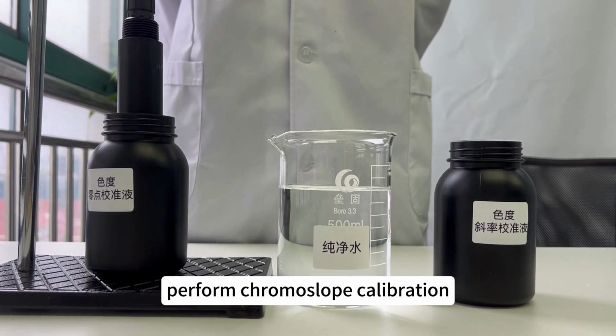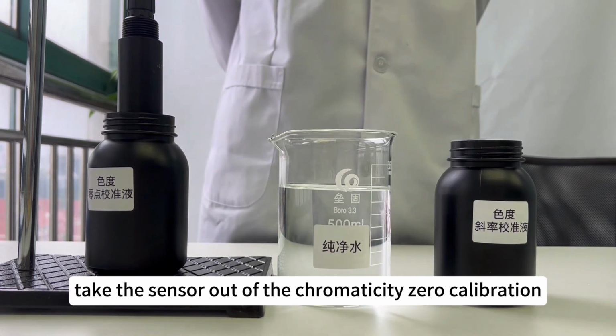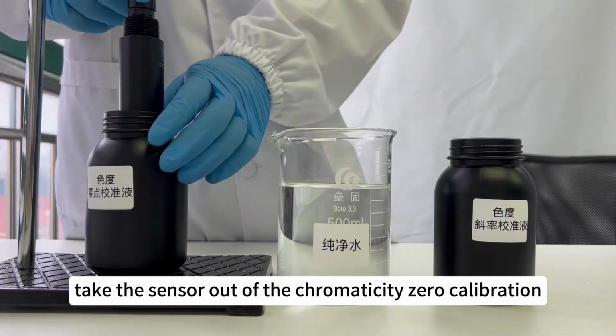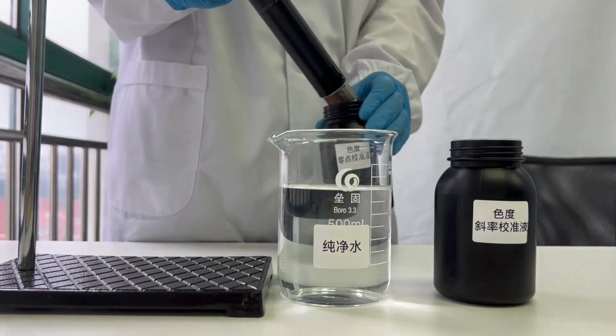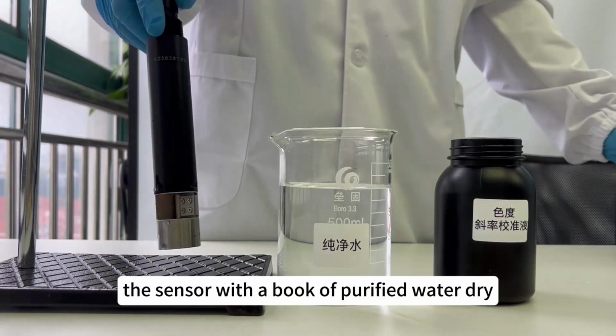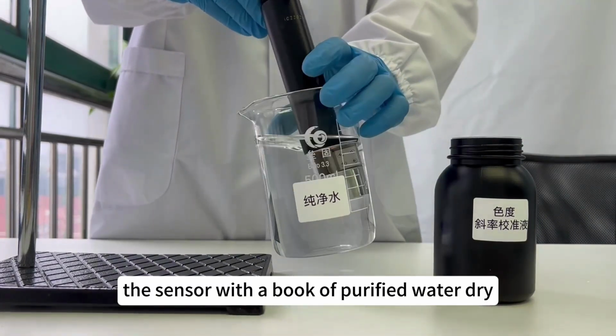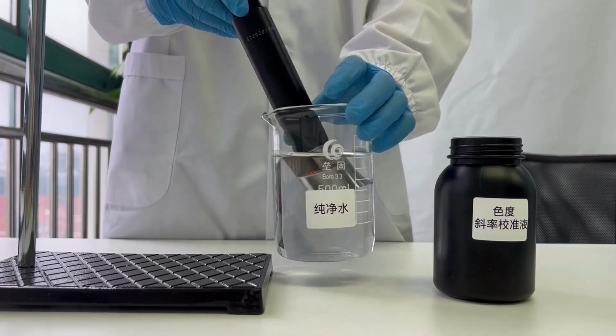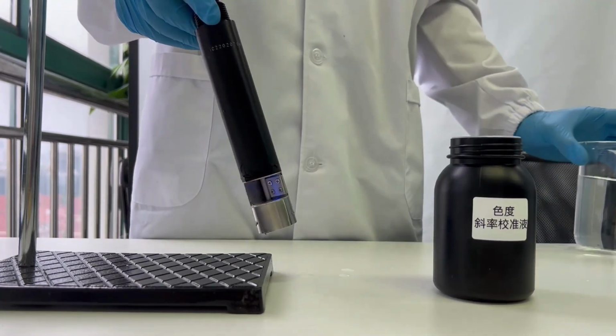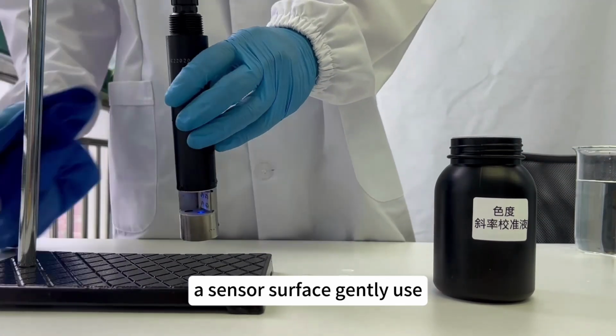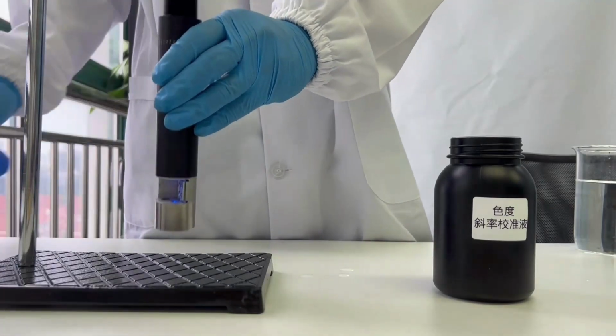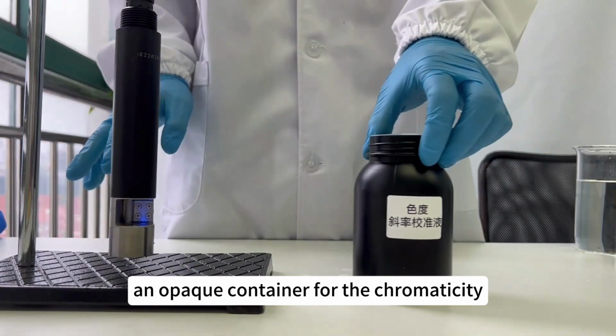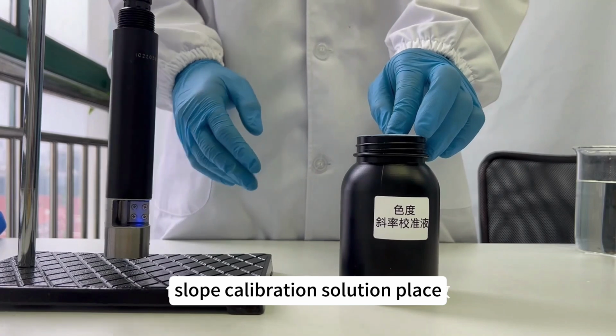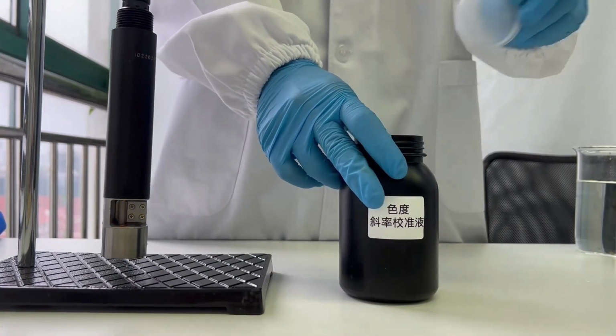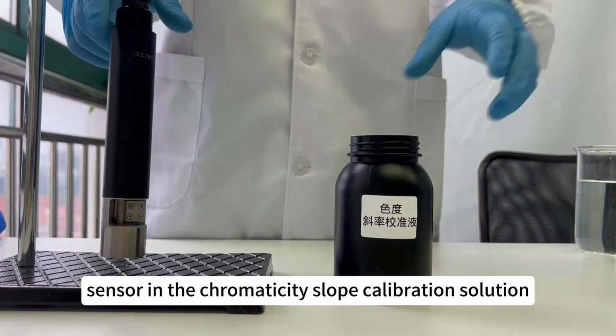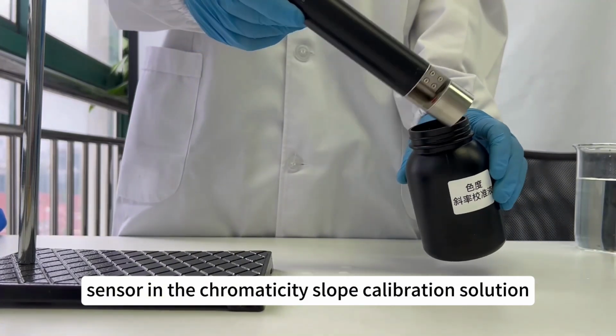Next, perform chroma slope calibration. Take the sensor out of the chromaticity zero calibration. Rinse the sensor with purified water. Dry the sensor surface gently. Use an opaque container for the chromaticity slope calibration solution. Place the sensor in the chromaticity slope calibration solution.